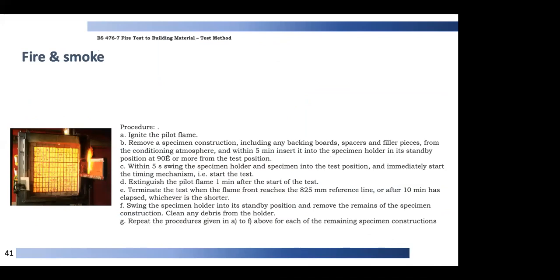This slide is included to understand fire classification, as so many fire incidents are happening. Every material burns when it comes in contact with fire because every material has its own burning point. But at what extent and at what level it burns is what specifies the material to be class O or class 1. This is the BS476 material testing procedure — a pilot flame is ignited and the specimen of insulation is brought into contact with the pilot flame to observe the behavior.